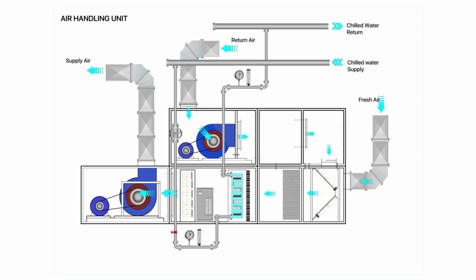The cooling process of an AHU is done by chilled water. So we have here a chilled water supply going to the cooling coil, and then the chilled water will exit here and return to the chiller system. In order to choose the sensors to be used for an AHU system, let's first go over a list of sensors and devices that we can integrate with the AHU system.